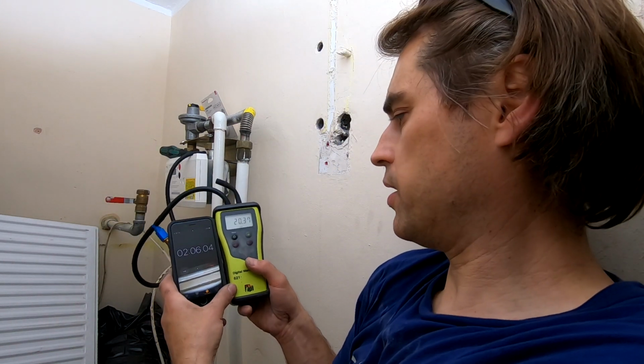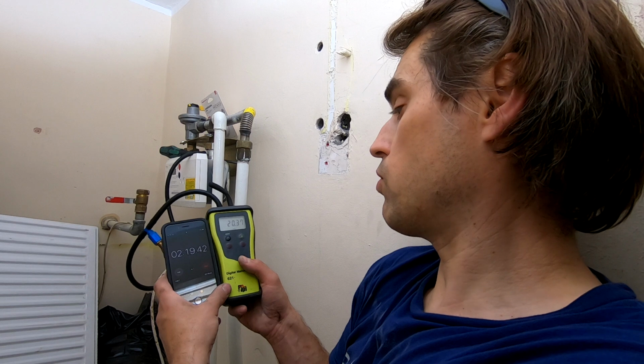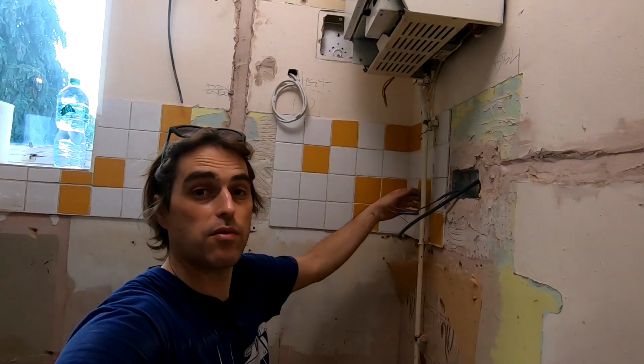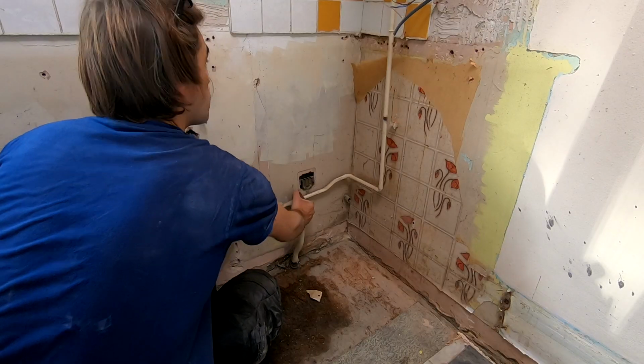So before I do any work on the boiler, on the gas line, I check the tightness of the installation, but there's no drop at all. This whole installation is sound. So I'm gonna remove this pipe and then remove the boiler off the wall.